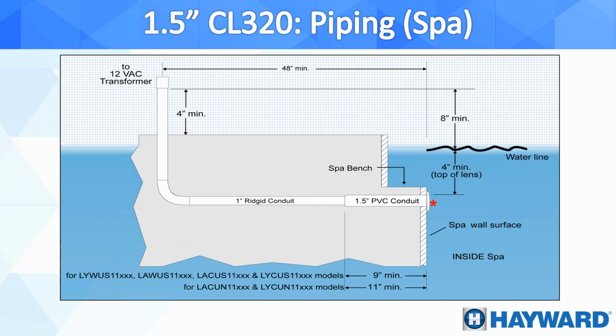Here we can see a similar installation. In this case, we're doing it on a spa. Here we can see the spa bench, and our lighting is going to be below the bench. Same recommendations: minimum 48 inches away from the water and 8 inches above the water level.